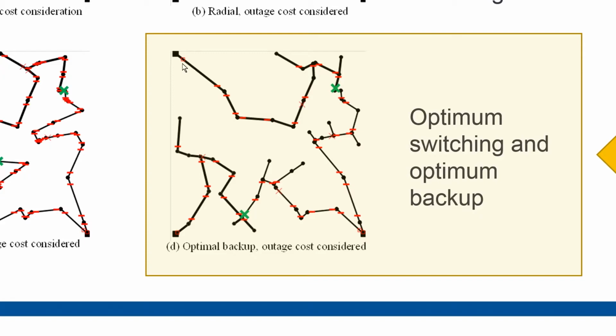So in this network we have, these will be the primary substations, these three corners here that are supplying the network. These will be the secondary substations that are consuming the electricity. We do have some parts of the network along a trunk line, like this one here. We do have an open switch here, a normal open point, meaning that there is one feeder coming from this substation that is supplying this area in normal operation. We have another feeder that is supplying this part of the network in normal operation, and a third one from this substation here.